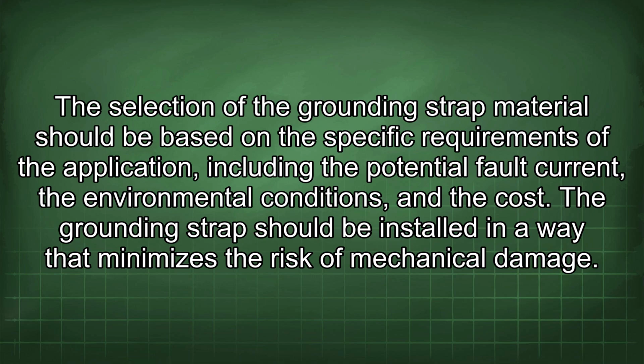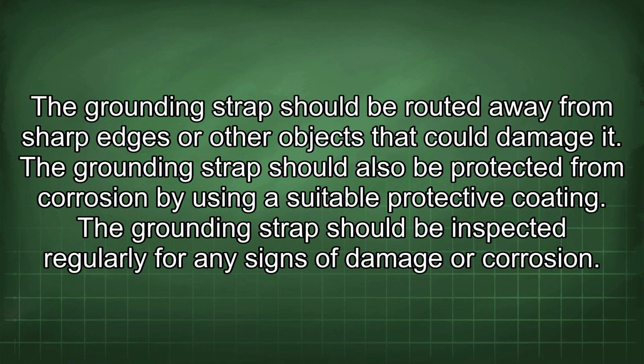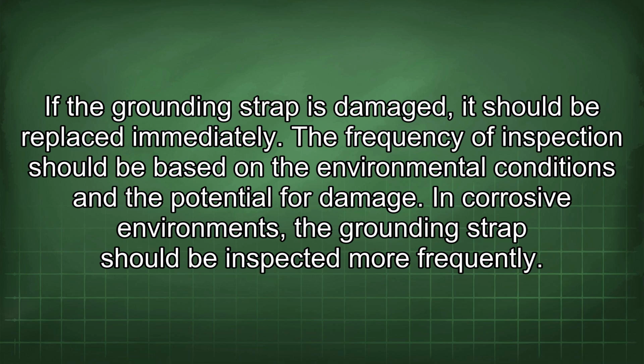The grounding strap should be installed in a way that minimizes the risk of mechanical damage. The grounding strap should be routed away from sharp edges or other objects that could damage it. The grounding strap should also be protected from corrosion by using a suitable protective coating. The grounding strap should be inspected regularly for any signs of damage or corrosion. If the grounding strap is damaged, it should be replaced immediately. The frequency of inspection should be based on the environmental conditions and the potential for damage. In corrosive environments, the grounding strap should be inspected more frequently.